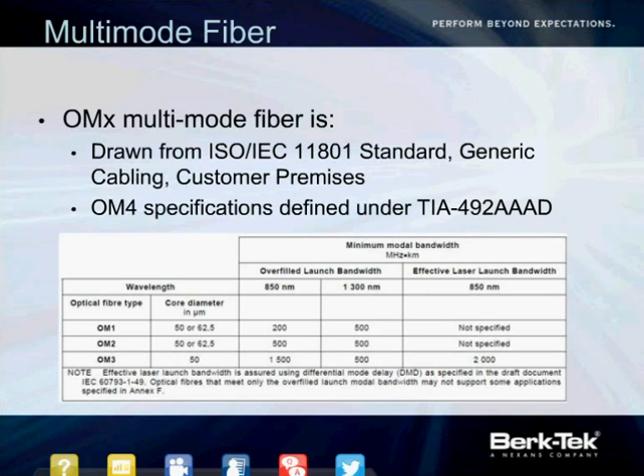The OM classification comes from ISO/IEC 11801, Table 27, which specifies the fiber type, its bandwidth, and its corresponding OM value. Back when this was written, OM1 could be either 50 microns or 62.5, likewise for OM2. If you read the 40/100 gigabit standard, you'll notice that for multimode it specifies a minimum of OM3. Keep that in mind as you move forward with your spec.